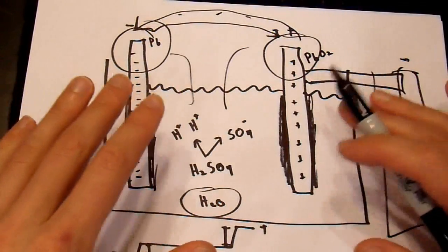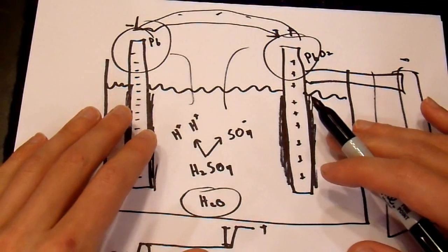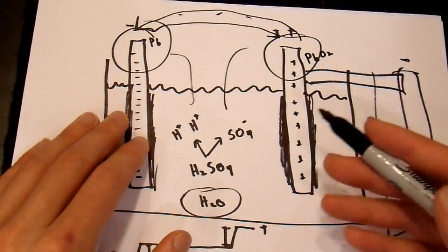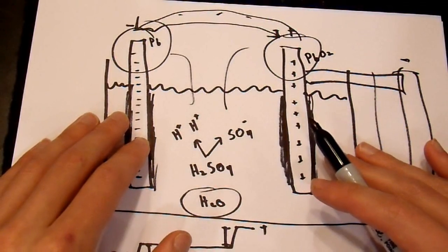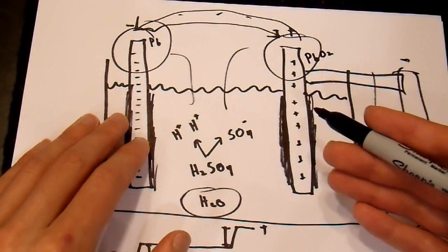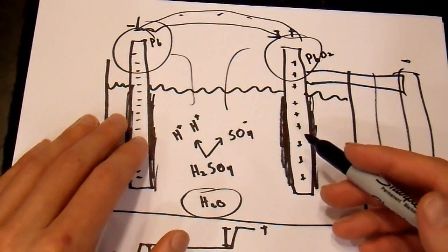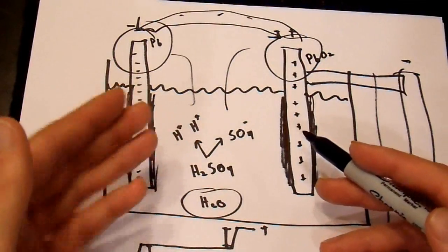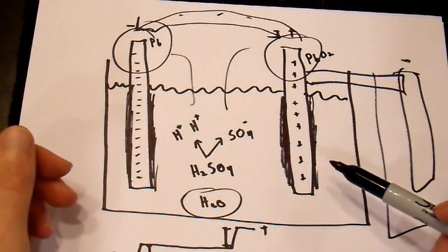To be exactly correct, I have to say that discharge rate has a very small effect on the capacity of your battery, as does temperature. Because, batteries will gas much quicker when it's hot. In fact, if it gets too hot, they can go into a runaway condition and destroy themselves. And, also, if you discharge or recharge a battery very quickly, it outgasses more. Less of it gets a chance to recombine.